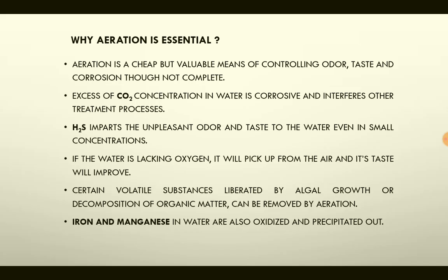Now the question is why aeration is essential. Aeration is a cheap but valuable means of controlling odor, taste, and corrosion even if it is not 100% efficient. Excess CO2 concentration in the water is corrosive and it interferes with other treatment processes as well as being detrimental to the downstream auxiliaries.